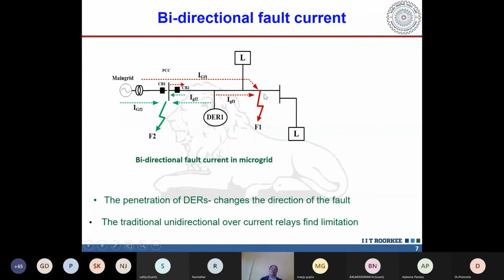On the downstream side there is a fault incepted here, and the red colors show the currents coming from upstream to downstream. But now let's say we create another fault on the upstream side bus, the PCC bus, the green one. For this fault point, the main grid fault current contribution direction remains the same, but the DER current contribution is reversed, coming from the downstream side to the upstream side.